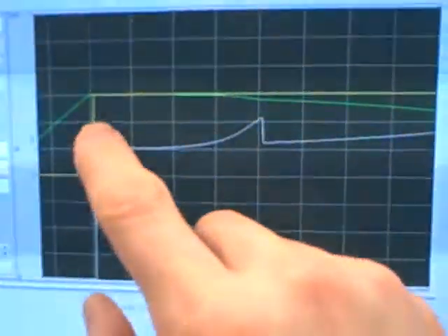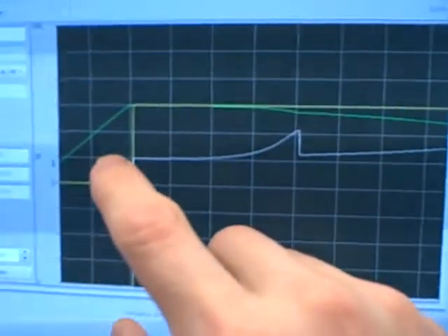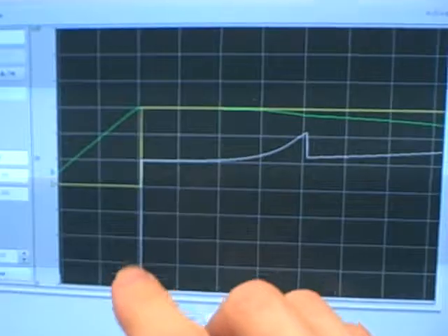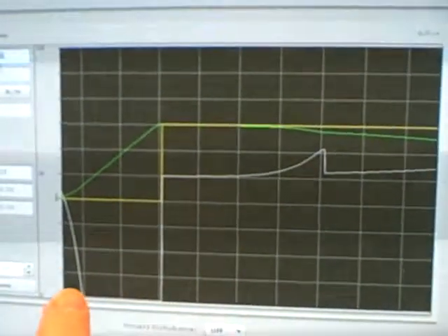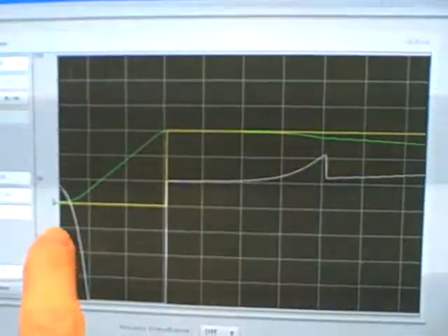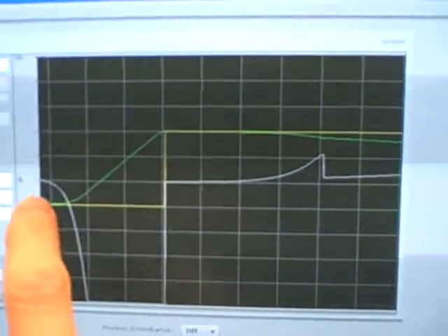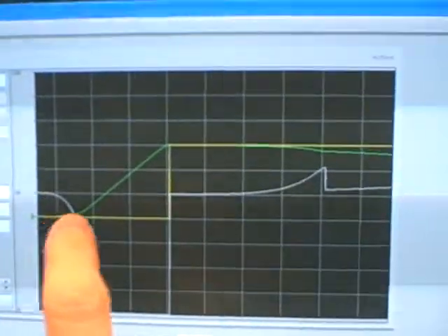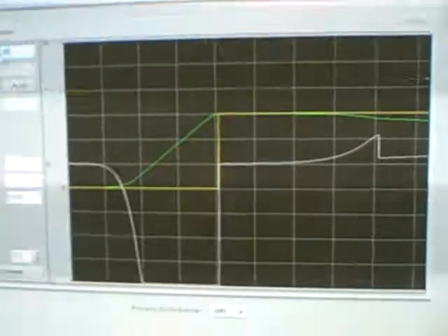And we can see the level is integrating downwards at a rather fast rate, meaning we're draining liquid from the tank and adding nothing to it. As we approach the new set point, we're going to see the valve position come up. There it goes. The valve position comes up and eases into its original position, its bias value of 50%. And you can see that our process variable achieves this new set point with no overshoot whatsoever, even with a fairly aggressive gain of 10.